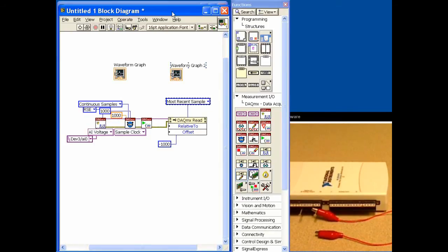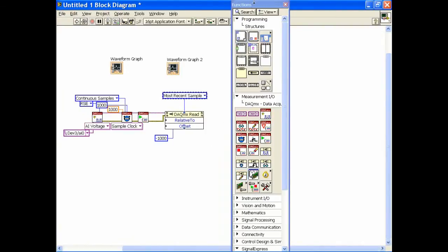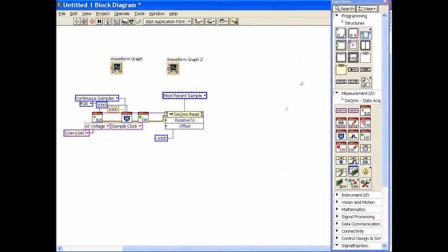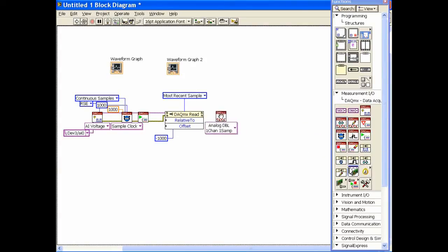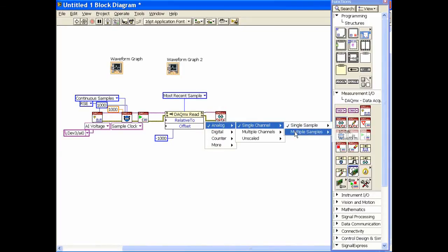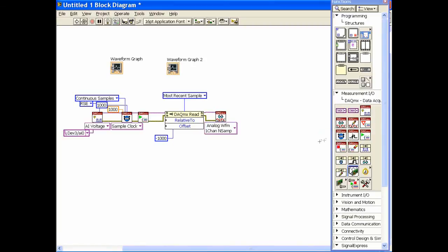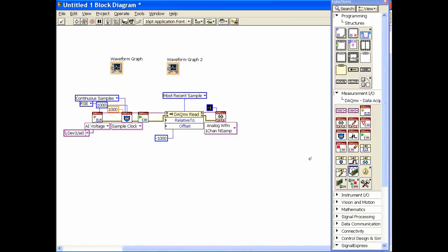Now we'll perform the actual read. Let me expand the diagram so you can see it better. We'll put down the read function — this will auto-wire if we get it close enough. I need to tell it to do analog input on a single channel with multiple samples and return data in waveform format. Then we'll create a constant and tell it 1000 points for the number of samples.